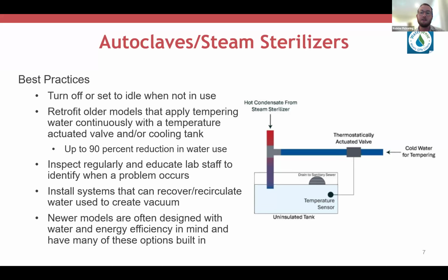And then lastly, there might be an opportunity to connect your sterilizer to the building chilled water loop as a heat exchanger to help cool your steam condensate and also to generate that vacuum for drying. These systems can also nearly eliminate all the additional water needed beyond just the water to generate the steam.